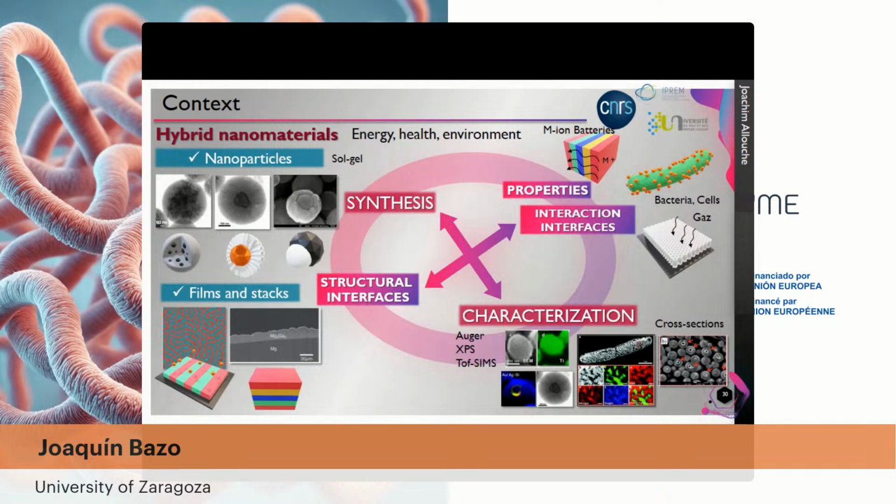Here, the data acquisition is quite slow, but if we change the samples to suspensions of nanostructures, those can be nanoparticles, cells, maybe microplastics, and we accelerate the data acquisition to the range of microseconds, the signal output changes. And now it's not a stable signal, but a series of intensity peaks that arise from a fluctuating background and provide information on the mass of those entities.